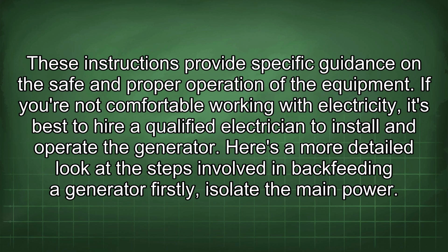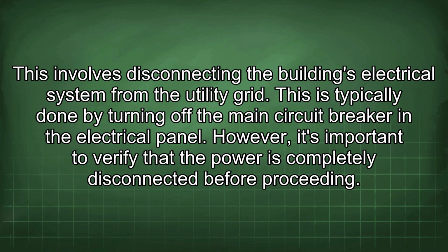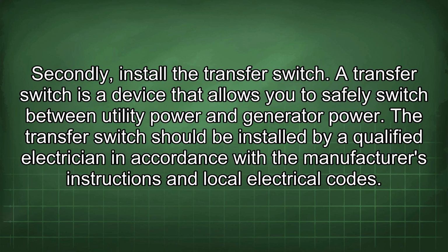Firstly, isolate the main power. This involves disconnecting the building's electrical system from the utility grid. This is typically done by turning off the main circuit breaker in the electrical panel. However, it's important to verify that the power is completely disconnected before proceeding. Secondly, install the transfer switch. A transfer switch is a device that allows you to safely switch between utility power and generator power. The transfer switch should be installed by a qualified electrician in accordance with the manufacturer's instructions and local electrical codes.